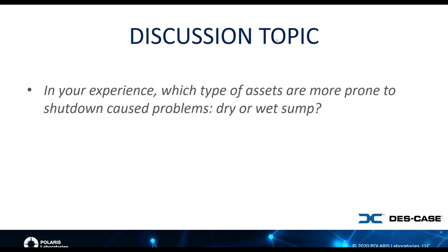But as Julio correctly said, if you've got a wet sump system, like a pump or a splash lubricated gearbox, if that oil is static and cool, when that oil cools, all the suspended material, whether it's oxidized oil or water that was dissolved, has now come out of solution, and that's when you start to see etching and corrosion on systems. And once you start to get that etching, you change the surface profile of your bearings or your gears, and the next time those bearings or gears engage, that surface profile is not adequate for proper lubrication. So again, you can think of scenarios where both cases are problematic, but I totally agree. Wet sumps generally are more problematic and need to be carefully thought about before you bring them back up to life.